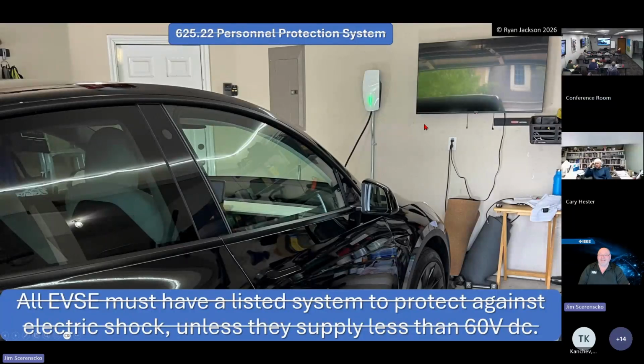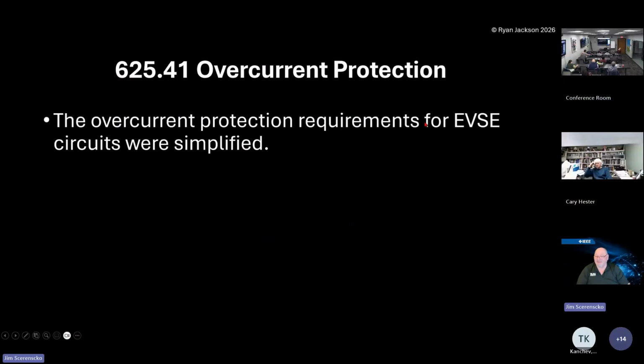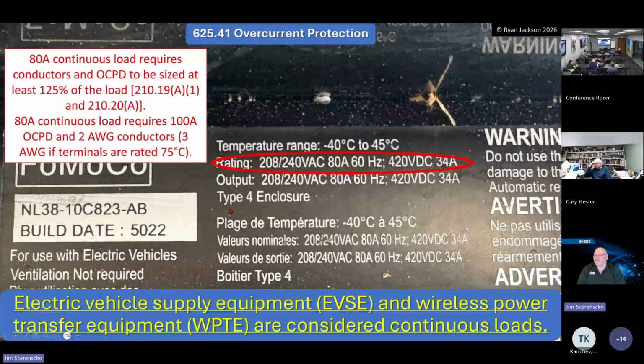That's funny. The overcurrent protection requirements for EVSE was simplified. Basically, an 80 amp continuous load requires conductors and an overcurrent protection device to be sized at least 125% of the load. An 80 amp continuous load requires a 100 amp overcurrent device and number 2 conductors, number 3 AWG if the terminals are rated 75 degrees. Okay, so you have to have all that information in order to size the circuit correctly.